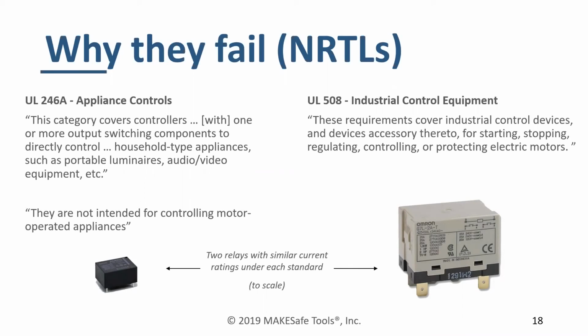As a quick comparison, these two relays shown here are to scale and have similar ratings, both good for up to a 15 amp motor. The one on the left is obviously tiny and not made to handle those arcs and sparks we showed, while the one on the right can handle that because it's been tested to a much higher standard. It's one of those things you wouldn't know unless you were crazy like me and dig through standards all day.